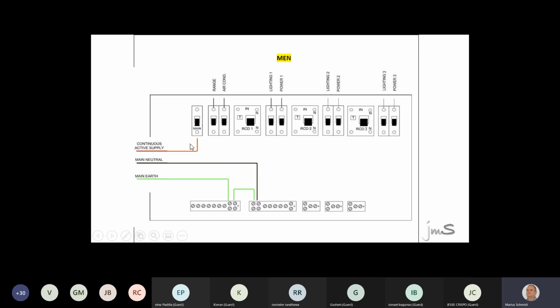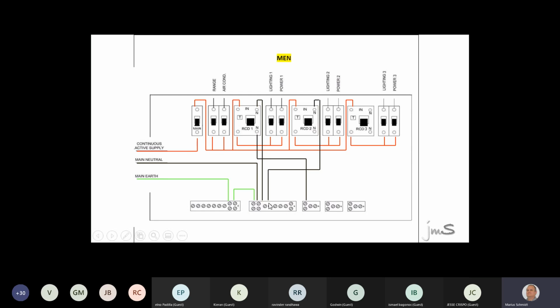Now, the supply comes in. There could be 2 breakers, which are not RCDs, and each one feeds. Now, guys, look at these RCDs. Can you see that each RCD is polarity conscious? In. Now, can you see that the bottom part goes out, the bottom part goes out, and the bottom part goes out? Now, do you all agree that all the earth is from the earth bar? All the non-RCD protected neutrals are from the non-RCD protected neutral bar, and each RCD subcircuit is from its own neutral bar. So each neutral is fed from the main neutral, and each one feeds its own neutral. And then obviously we just add the subcircuit.